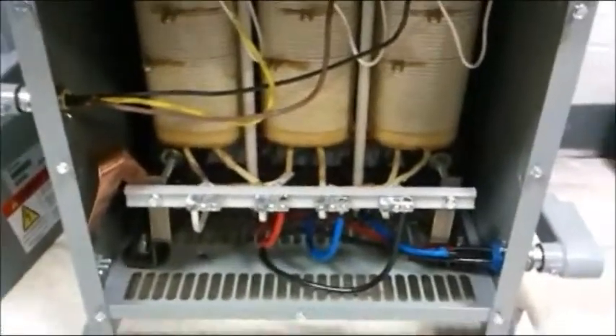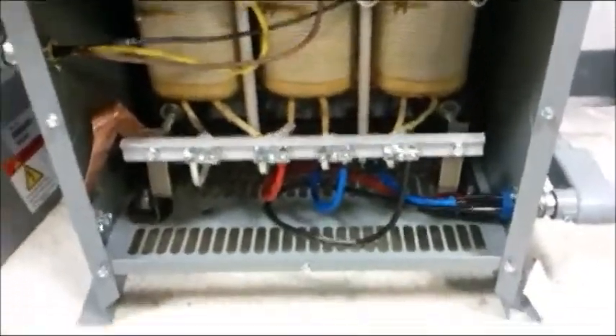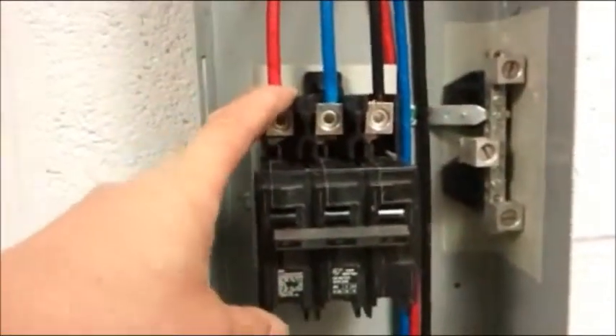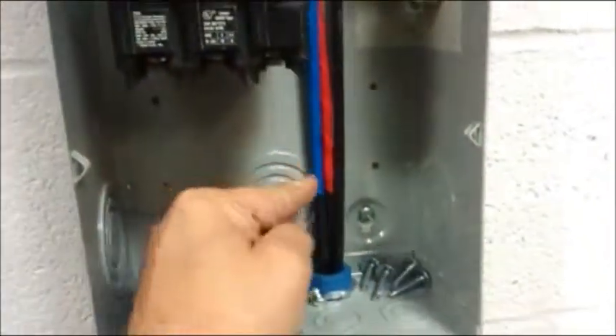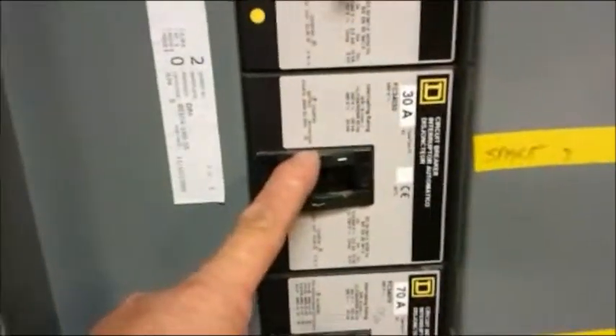Okay, I'm back here at Fallon, and I just want to show you the wires for the transformer that we got hooked up. I have the secondary side in here, and we color-coded the wires. Okay, here's our line side up here, which is being fed from the transformer down here, which will give us our 208. And yesterday I installed the primary side, which goes over to the panel, and it's going to be hooked up on this 30 amp breaker right here. Okay, it's off right now. The wires are not hooked up on the breaker yet. That'll be the very last thing that we do.